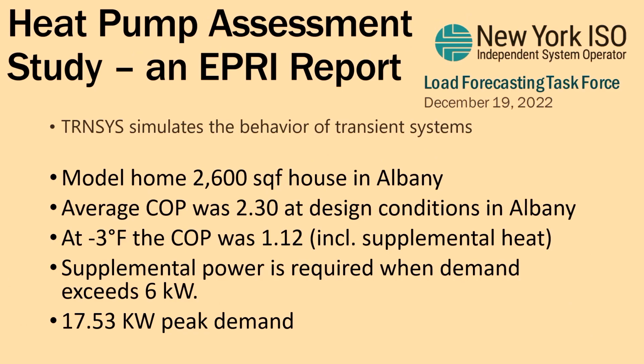We talked a lot about air source heat pumps because once you electrify, you have three choices: electro-resistance heat, which will collapse the grid; air source heat pumps, which in my opinion will collapse the grid on the worst day of the year; and ground source, which has no grid impact because it produces the same way regardless of conditions. This is what monitoring in the field has shown - they have the same COP whether it's 40 degrees outside or minus 40, it doesn't matter. NY-GEO actually looked at this with air source heat pumps.